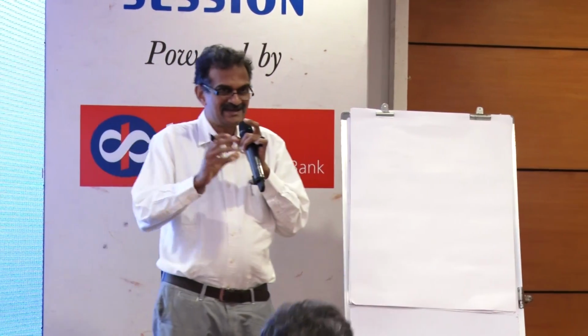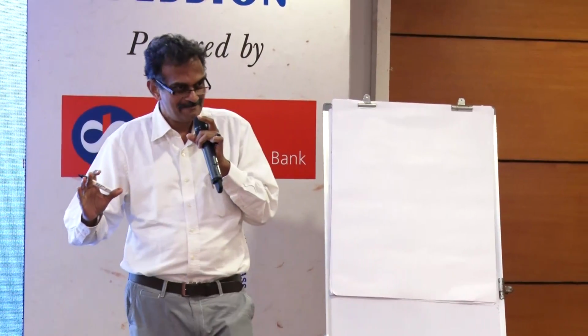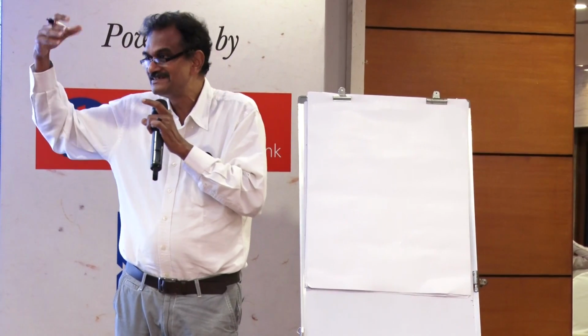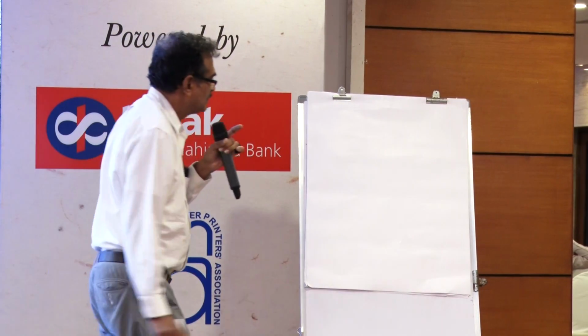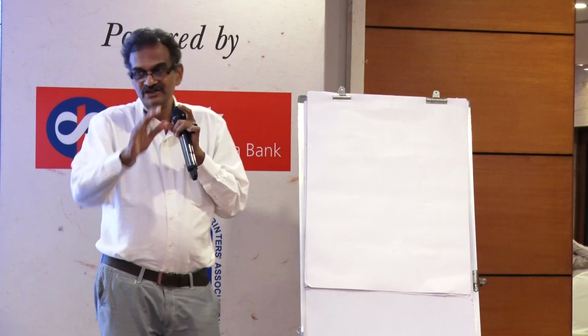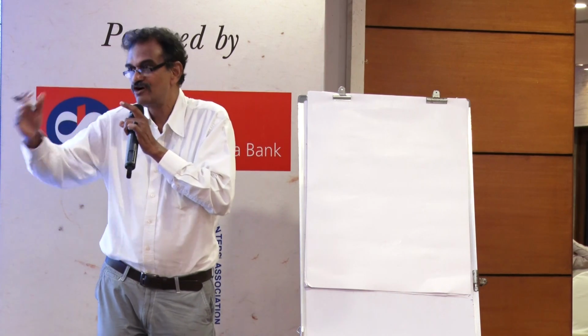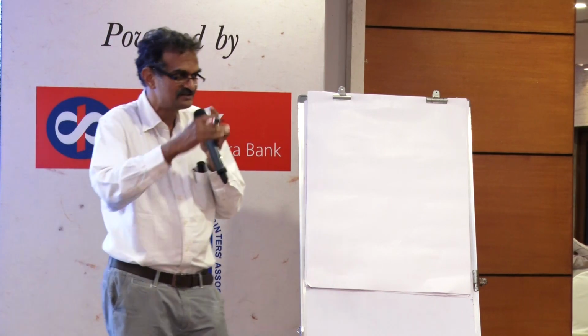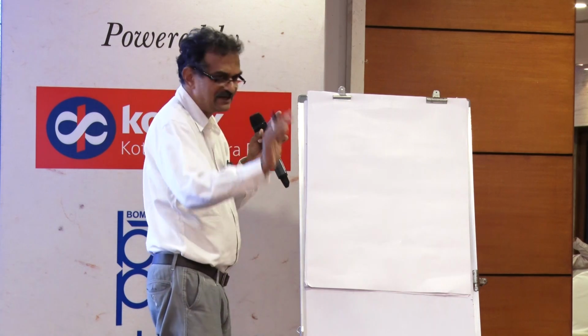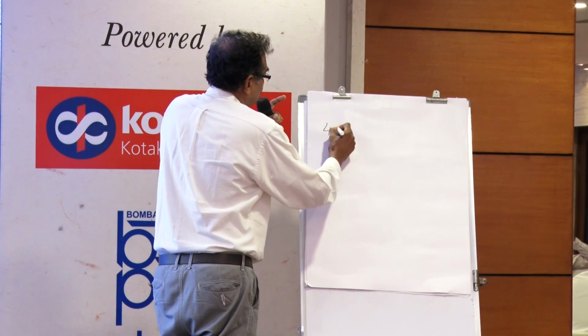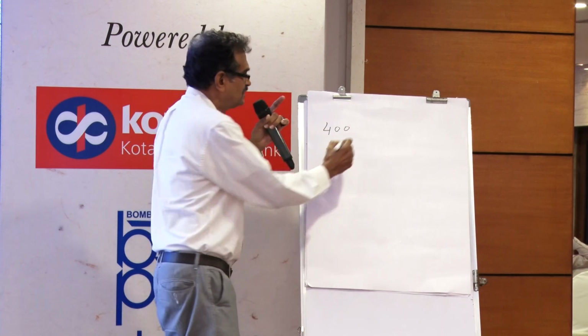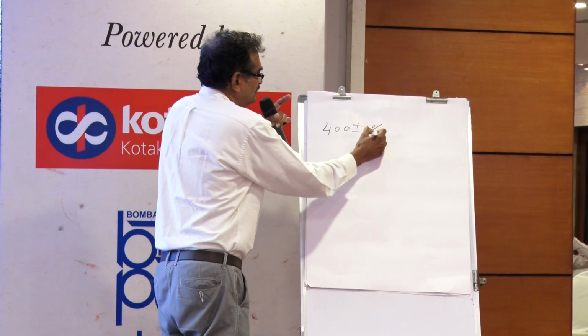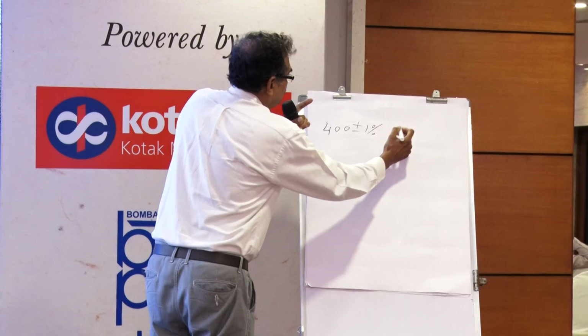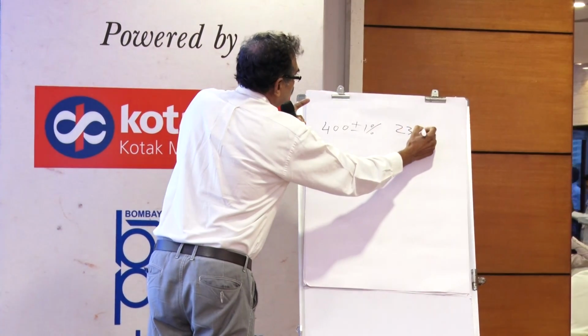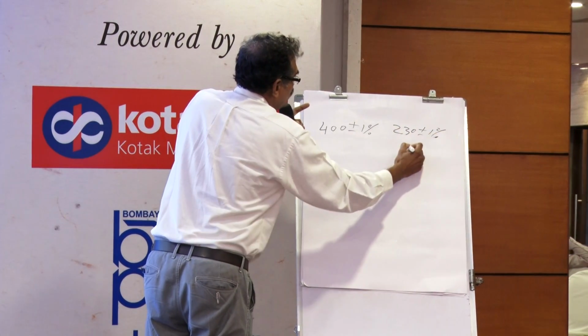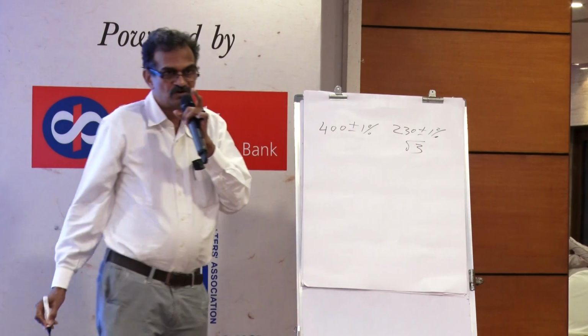I'll take an example of a single phase stabilizer, and then it can easily be seen from a three phase perspective. Let's say all our machines require 400 volts for example. Somewhere it's 380, somewhere 415, somewhere 400. I'll take a simple example of 400. So I want 400 volts steady, plus minus 1%. That means my single phase voltage needs to be 230 volts, plus minus 1%, and root 3 times this is nothing but 400 volts.